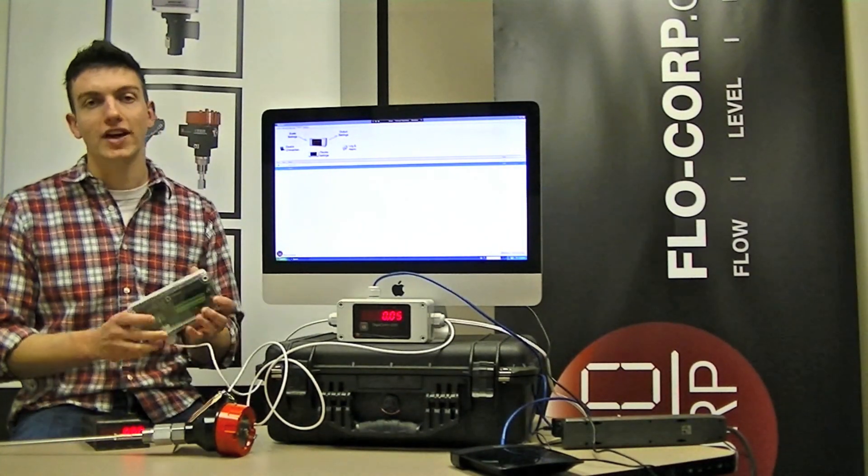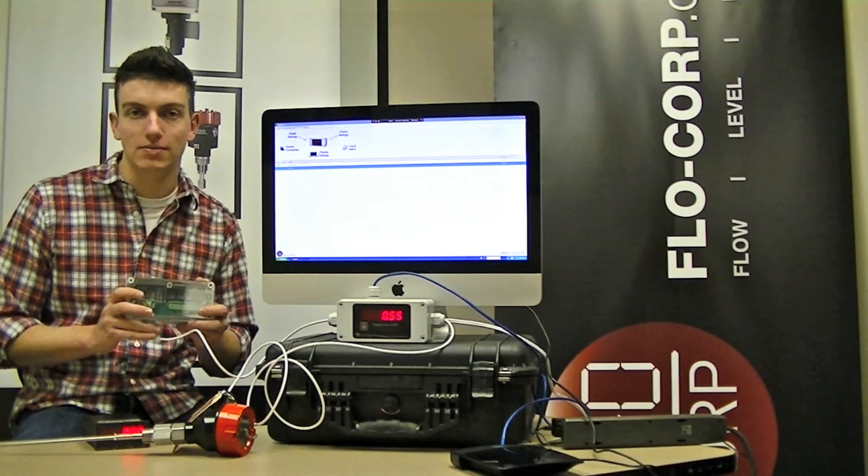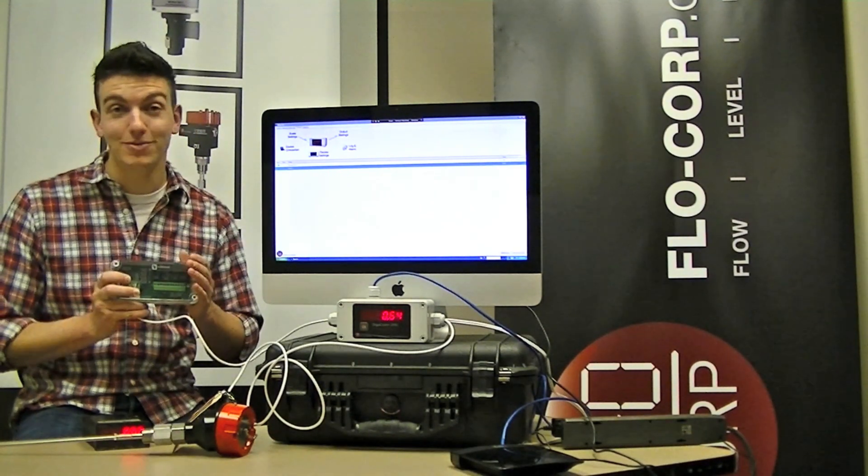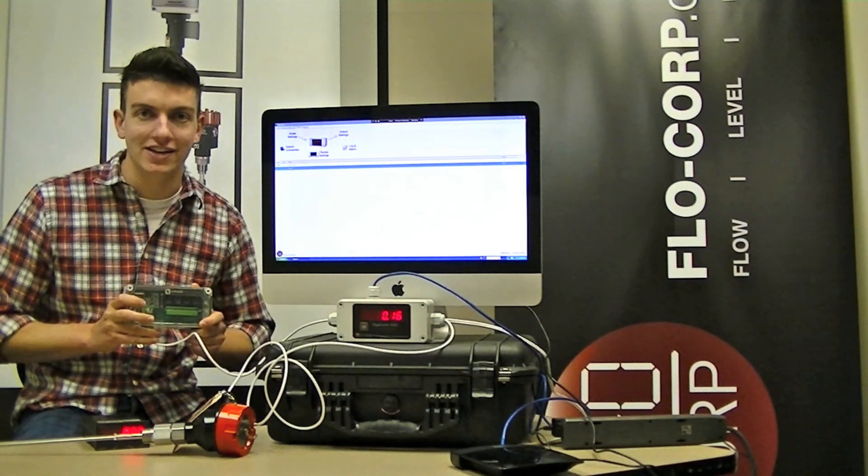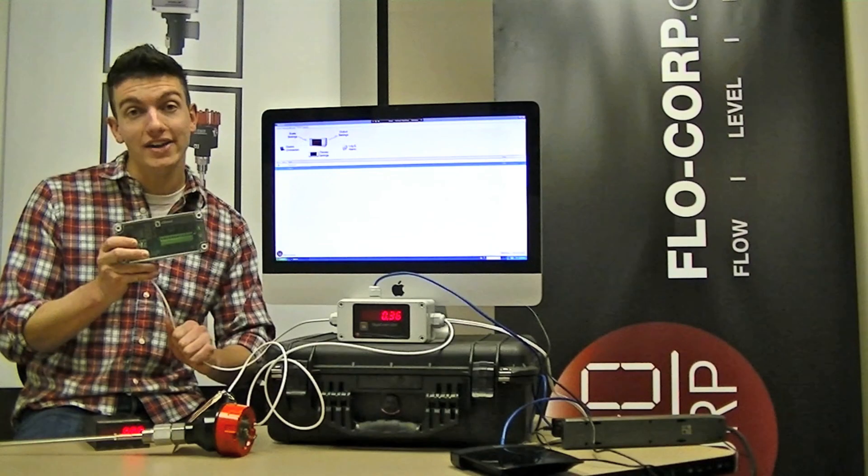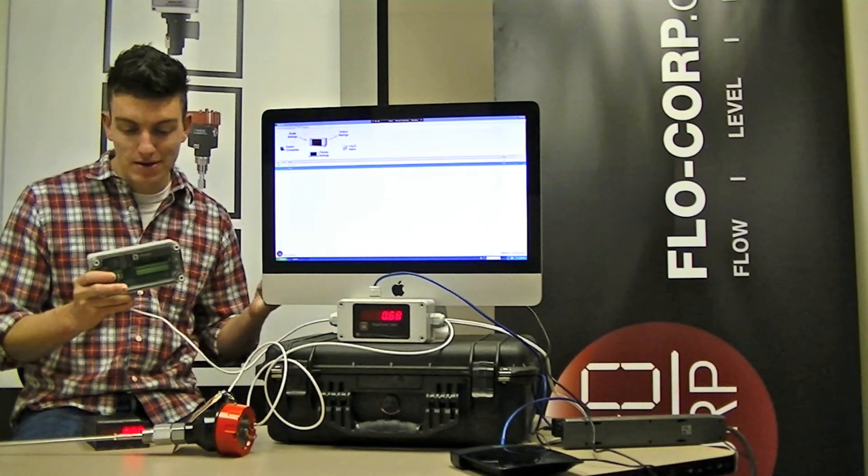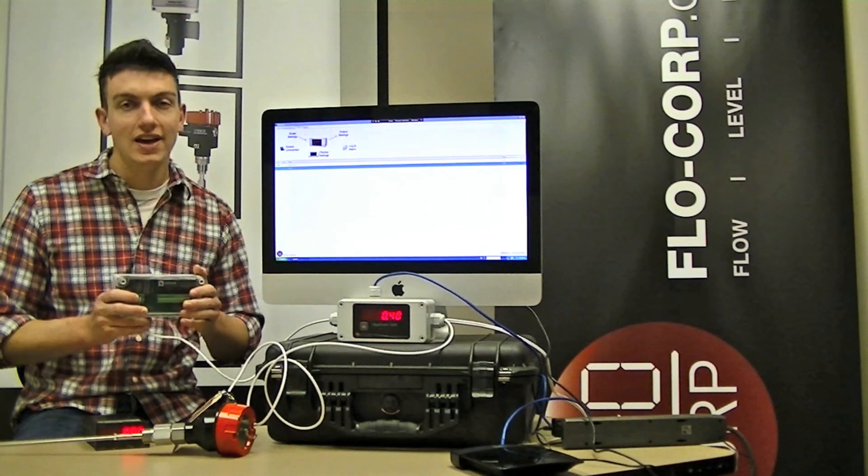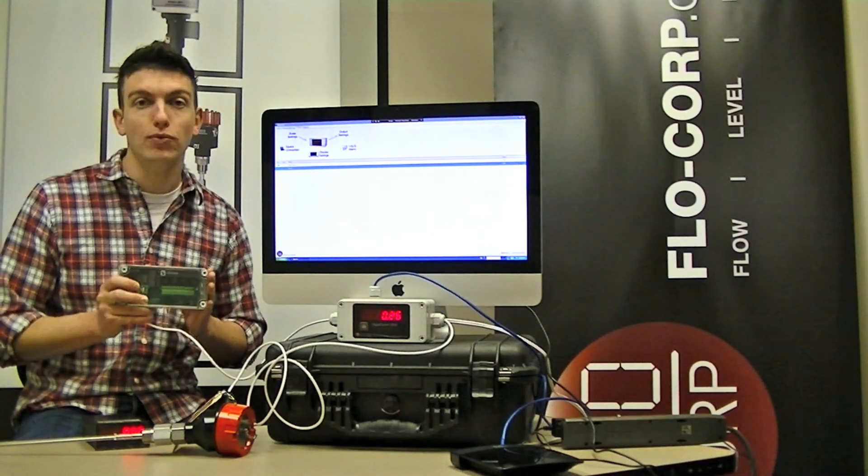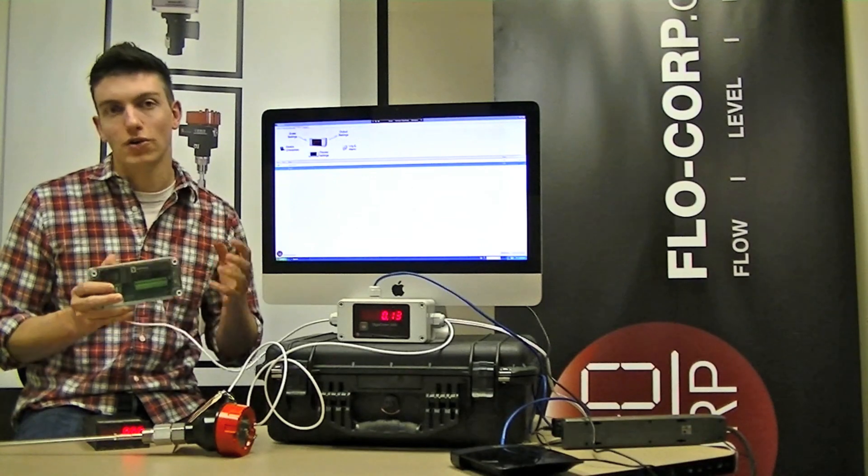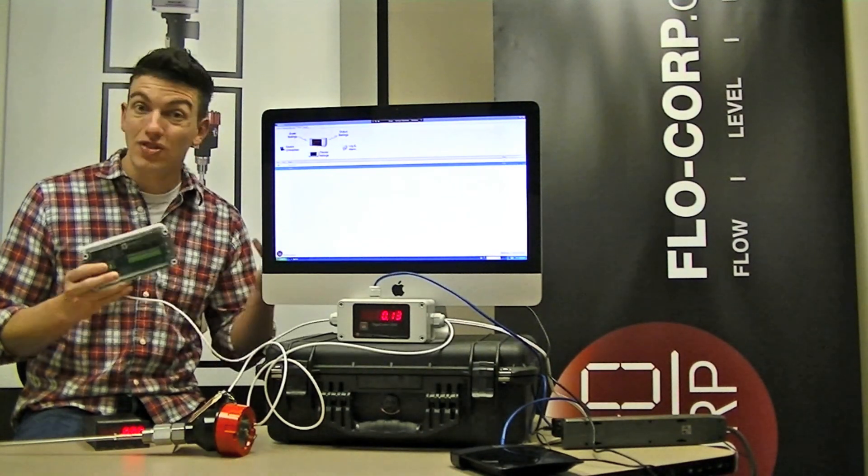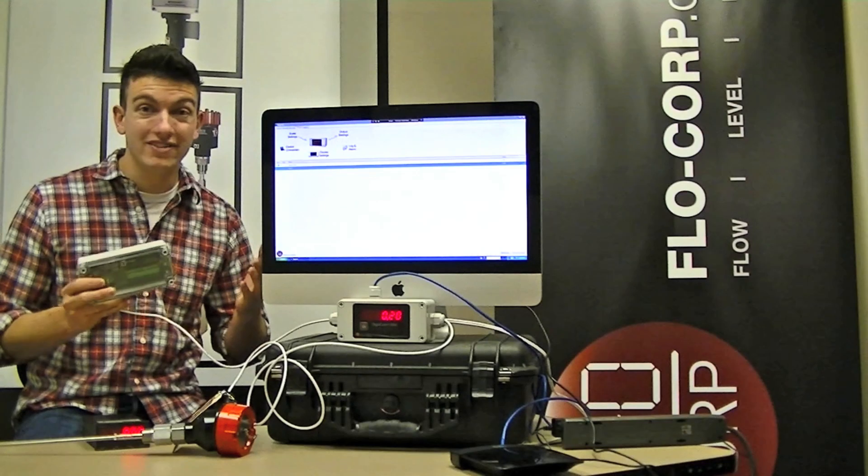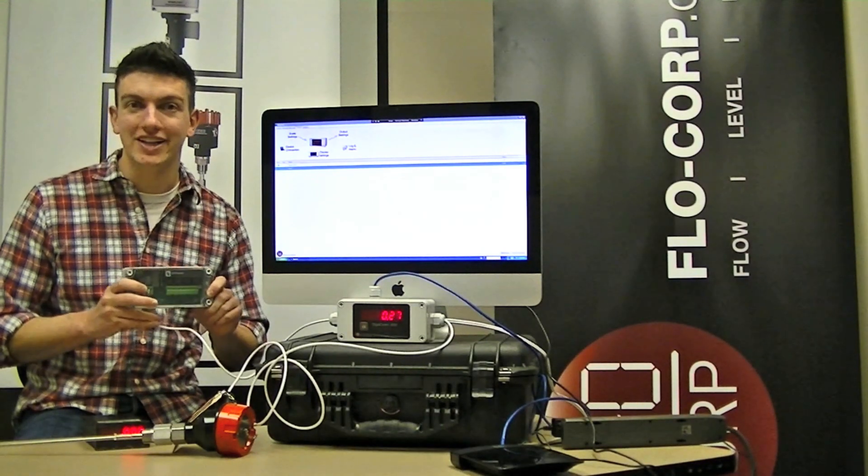And the final device in this lineup is the Xmod Relay Expansion Module. This is an awesome device, and it adds quite a bit of horsepower to our displays. It connects through RS-485 cable, which means it can be mounted even up to thousands of feet away from the display itself. It also has four 10-amp relays in it. This is excellent for controlling pumps, pump alternation, triggering alarms, controlling valves, or really anything you need to control with a relay.